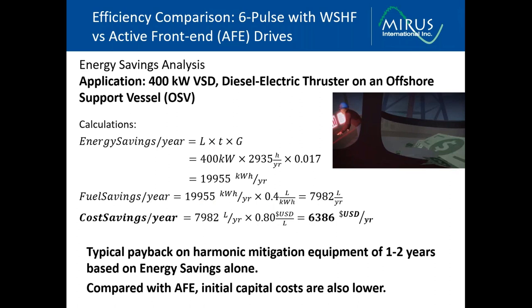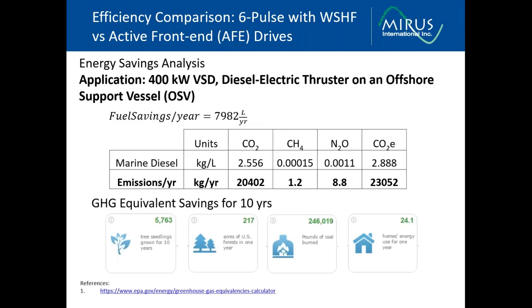So typically, you can see paybacks of less than 1 to 2 years on the passive harmonic mitigation equipment alone. Then when you factor in that the comparative active front-end drive system is a higher capital cost, that justifies the application even further. And of course, when we're reducing the energy consumption in a generator application, but also even in a utility application, we're going to reduce the emissions. If we do a quick calculation on this savings and reduction, you can see that over a 10-year period, there's a substantial positive effect on the environment.